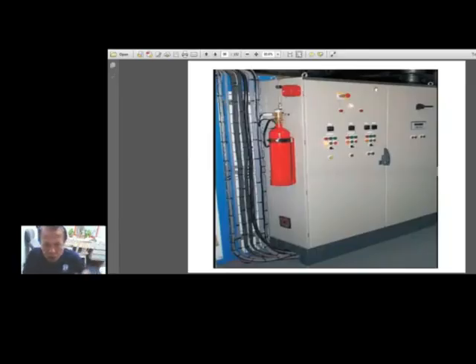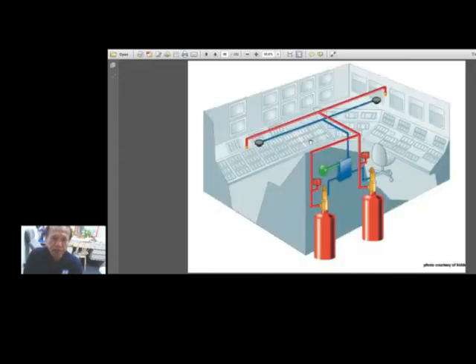Here is another installation where you have a switch gear, and you would have the agent in here with the piping. So that means the piping goes inside the switch gear, and therefore it would protect your switch gear against burning. So in a control room where you have a control desk console like this, you can also provide this type of protection with nozzles on both sides. So this is to protect your equipment the moment there is a heat or a fire or an arc flash that may happen, then it would operate immediately.